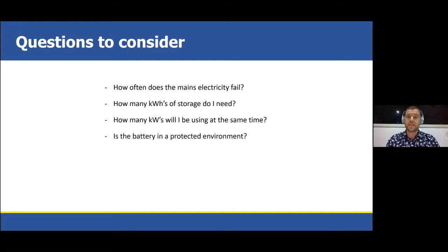We have seen, you know, the Tesla Powerwall battery, I think, is IP56 rated, so it can handle direct water from a nozzle. But it is better off in a protected environment that it's out of the way of dust and direct sunshine and water ingress, if possible. And it's also got some temperature restrictions as well. When they're installed in a shed in summer, for example, most batteries just don't perform as you would expect.